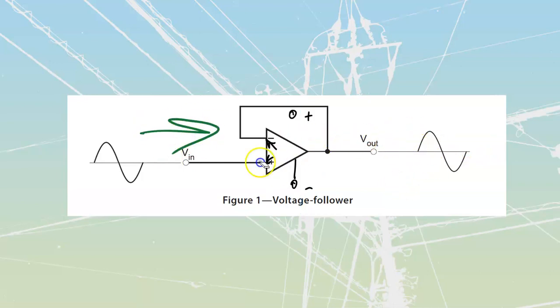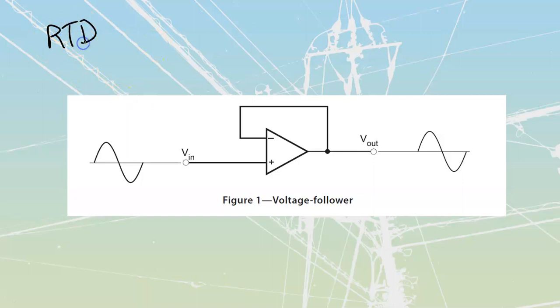And that's really handy for us because there are a lot of cases where we have small and weak signals coming in. A prime example of something like that would be an RTD. If you're not familiar with RTDs, something that as you get further on into the industrial, the automation end, you're going to see more of, it's called a resistive temperature device. Really, it is going to be a positive value of voltage that we will attach. It's going to be DC usually. And then that DC is going to go through a resistance, and that resistance type of material is going to have a voltage drop on it.